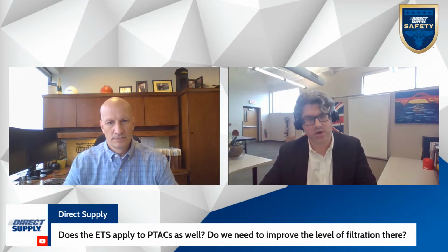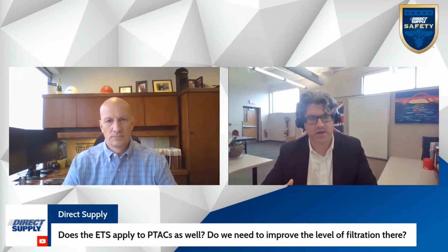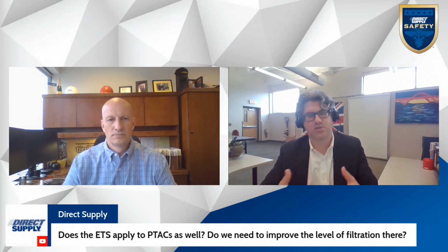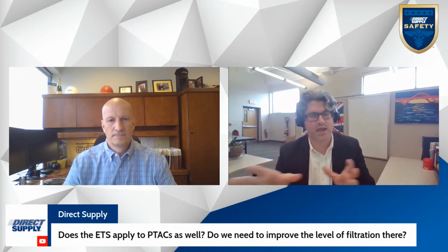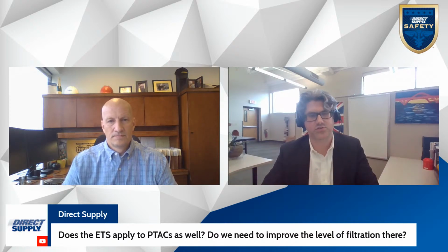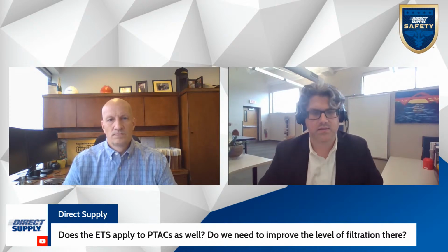What I would say though, depending on the PTAC you have, you can influence the amount of outside air it's taking in. Again, work with the manufacturer guidelines and specifications - you can maximize the amount of ventilation, the air changes per hour, relative to how it's designed. So it might fall in the ventilation bucket. I'd be very surprised if it falls into the filtration bucket, but that's something we can try to get clarity on, and we'll keep everyone updated as much as we can.